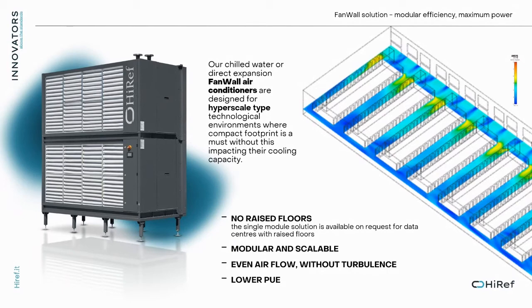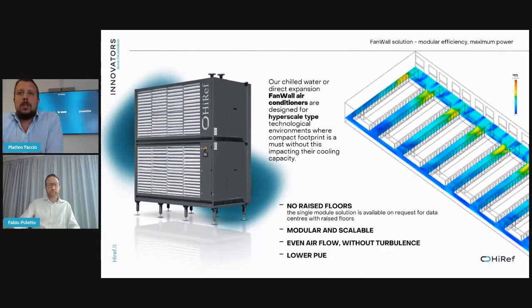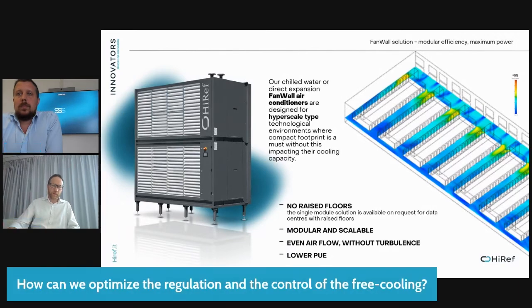So it means that we can save money on the technical floor. We can also save time, because normally it takes time to build the whole double floor system. And this unit is modular and scalable, and thanks to the really low pressure drop of the system, we can lower the PUE and get really good performance of the cooling distribution. Okay, now it's clear how it's possible to optimize free cooling on the production of the cold water and in the distribution of the load. But there is something that we can do also in the regulation, in the control of the two sides, in order to increase and optimize the use of free cooling.